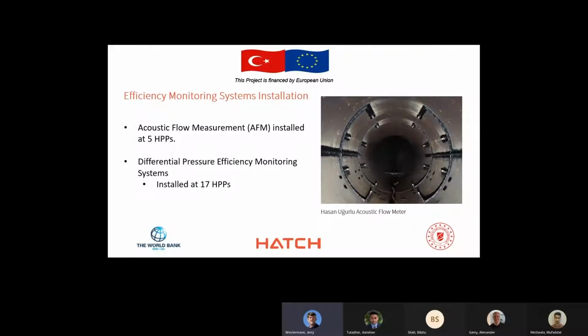These systems were used to essentially come up with a signal that could be used to determine the flow very accurately, though they did require calibration using another temporary method of flow measurement. I should point out that with one exception, only one unit at each one of these HPPs was fitted with a flow monitoring system. The one exception is Ataturk, where all 8 units were fitted with a differential pressure efficiency monitoring system.